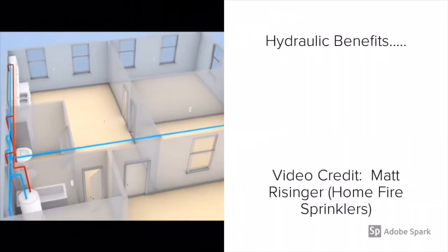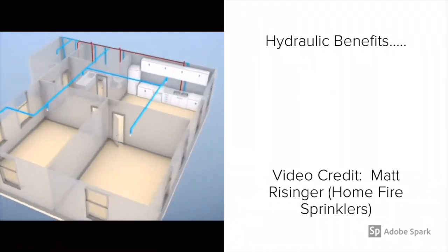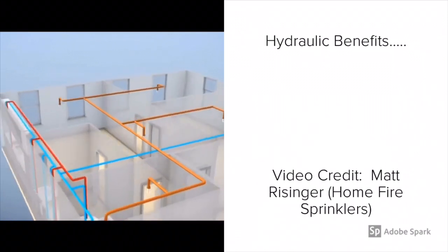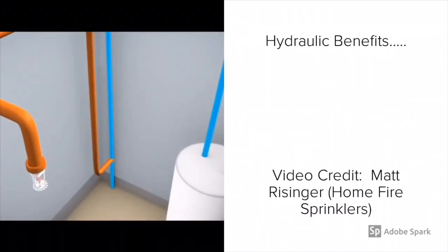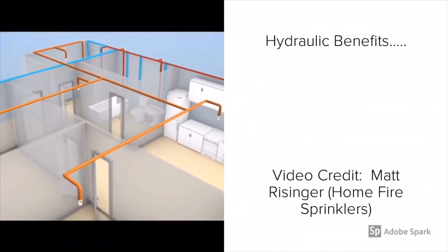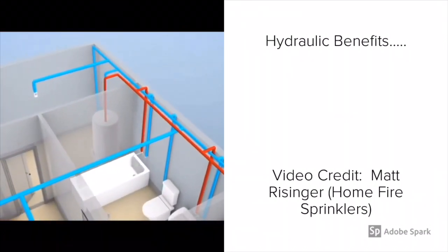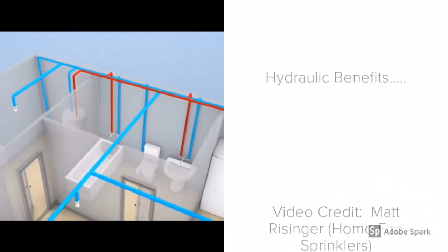Residential sprinklers have a significant hydraulic benefit. Based on the ability to better fight a residential fire, the use of a residential style sprinkler has a hydraulic benefit that dramatically helps the hydraulic calculations for a residential area. So typically what you see is in a 13D type application, 2 heads flowing for 10 minutes. In a 13R application, you see 4 heads flowing for 30 minutes.